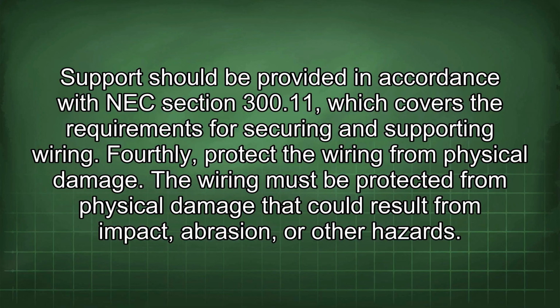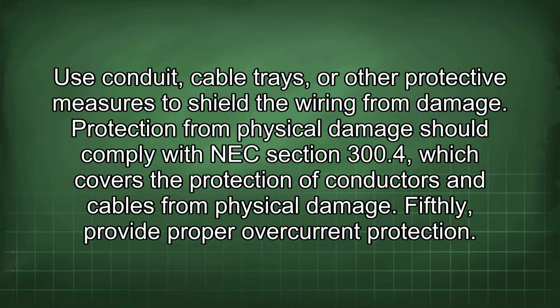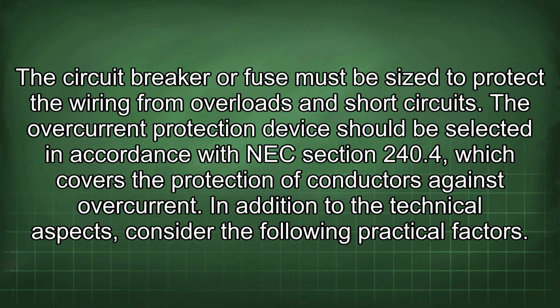Fourthly, protect the wiring from physical damage. The wiring must be protected from physical damage that could result from impact, abrasion, or other hazards. Use conduit, cable trays, or other protective measures to shield the wiring from damage. Protection from physical damage should comply with NEC Section 300.4, which covers the protection of conductors and cables from physical damage. Fifthly, provide proper overcurrent protection. The circuit breaker or fuse must be sized to protect the wiring from overloads and short circuits. The overcurrent protection device should be selected in accordance with NEC Section 240.4, which covers the protection of conductors against overcurrent.